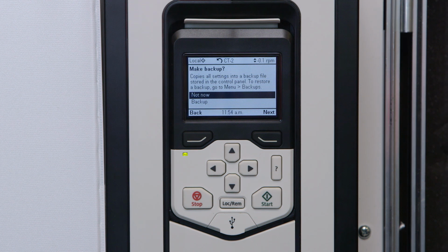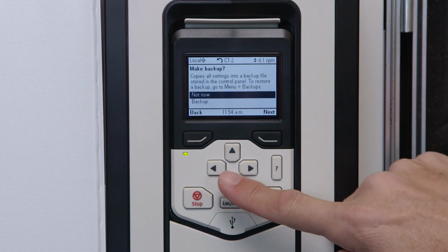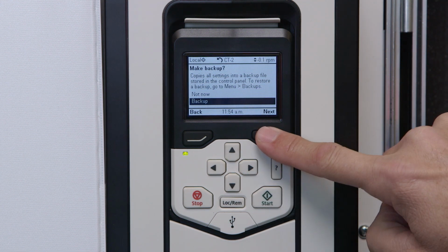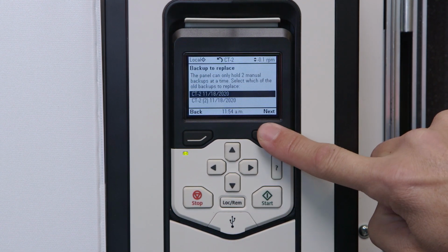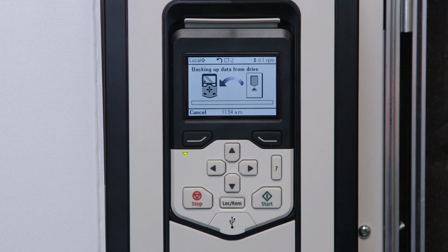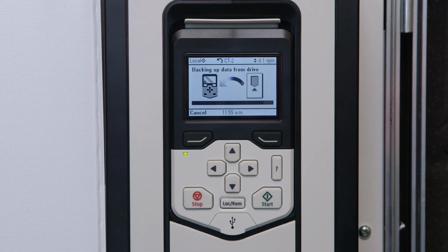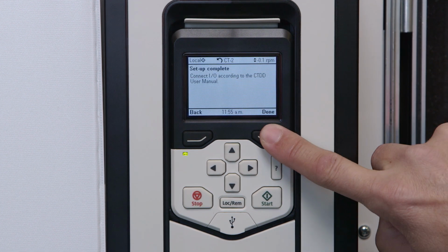Before completing the cooling tower setup, use the screen to copy the VFD parameters to the keypad as a backup. To do this, scroll to the backup option and press Next. The display will show an activity bar highlighting the backup in progress. When the bar indicates that backup is complete, the display will show the message "Backup Complete." When you see this message, press Done.